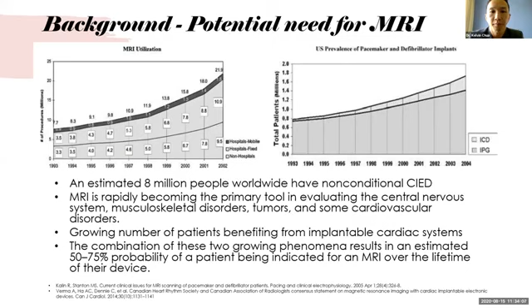So some of the definitions that we'll be using today, just to make sure we get this straight, is that there is no cardiac device that can be labeled as MRI safe. MRI safe labeling requires the object to be of absolutely no hazard in any MR environment. An example would probably be plastic objects. An MR conditional device would be an object that's been tested in a specific MR environment with specified conditions that has been proven not to pose any hazards. This often requires combined knowledge of the MR factors and our device's lead and generator specifications. And of course, an MR non-conditional system would include any devices other than those meeting the MR conditional labeling.